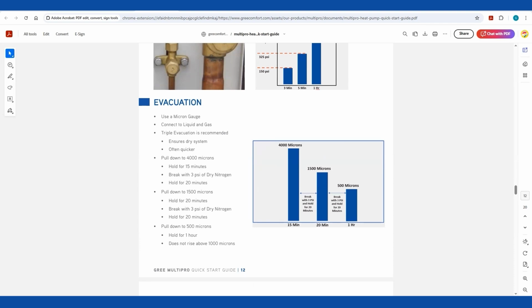So we want you to pull it down to 4,000 microns, break it with nitrogen. You don't need a bunch of pressure there when you break with nitrogen. About 3 psi is plenty just to displace any air that might be in there. And each time you do this, you're going to find it's going to pull a vacuum much faster. So 4,000 microns for the first pull, 1,500 microns for the second pull, and your last pull, you want to be down 500 microns or less.